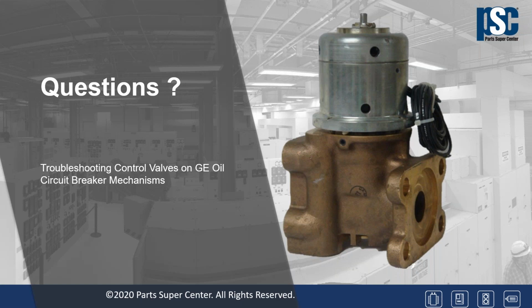There's one more here that talks about, are these valves able to be remanufactured? In general, we recommend that if you have a valve that is leaking, that you replace it with a known good valve. These valves, as most of the people that have worked on these know, only leak when it's -2 degrees out on a holiday weekend. So we, in general, recommend that the quickest fix is usually to replace it with a new or even a remanufactured valve.